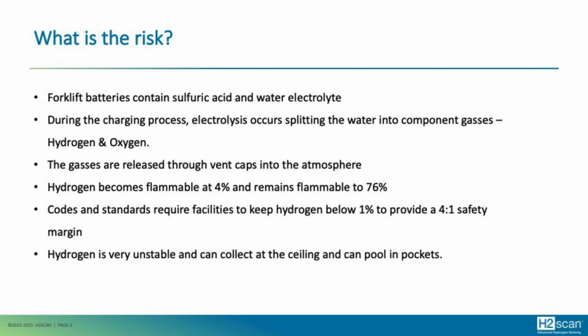This is also being adopted around the world as codes and standards change to provide this safety margin when dealing with hydrogen. Lead acid batteries are not the only batteries on the market, and there are other batteries that have different gassing properties and also much faster gassing if a battery were to go into thermal runaway. Even though this presentation isn't about lithium batteries, just for example, lithium batteries gas a whole lot faster if they go into thermal runaway compared to lead acid batteries. Keep that in mind. That's why these safety standards exist, so that you have time to react to a situation. And hydrogen is very unstable, so even a light or a switch can ignite it very easily.